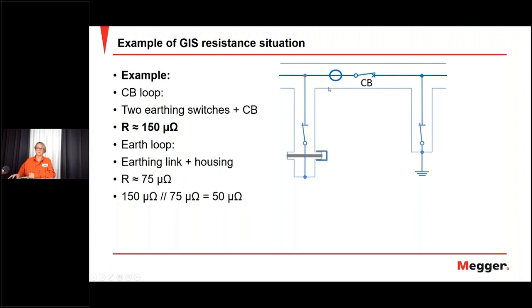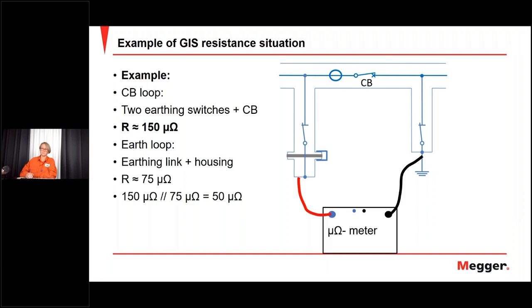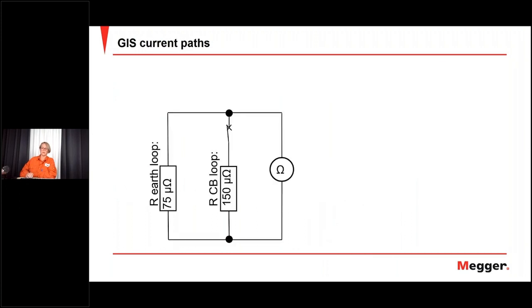The problem is, if you don't compensate, you will have a resistance also in the ground, and the earthing link and housing is as low as 75 microohms. So it's even less than the resistance you want to measure. And if you measure this in the wrong way, you would get 50 microohms. Connect the current, but it will go both ways, right? And the result will be 40, 50 microohms. Because as you see here, you have the micro-ohmmeter and you have a circuit breaker loop, but in parallel you have an earth loop.